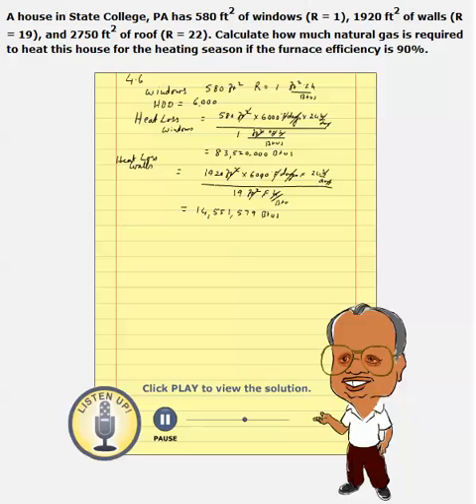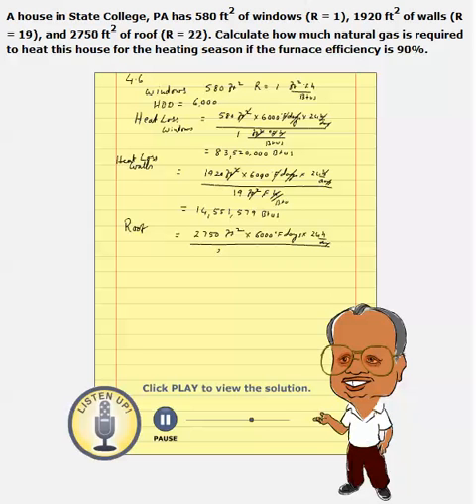Now we need to calculate roof heat loss. We use the same formula. The area is 2,750 ft², HDD is 6,000 degree-days, and there are 24 hours in a day, divided by the R value, which is given as 22 ft²·°F·hr/BTU. Canceling units, we get 18,000,000 BTUs from the roof.